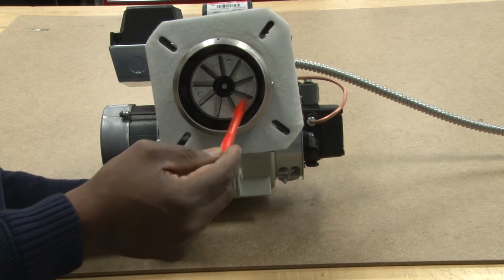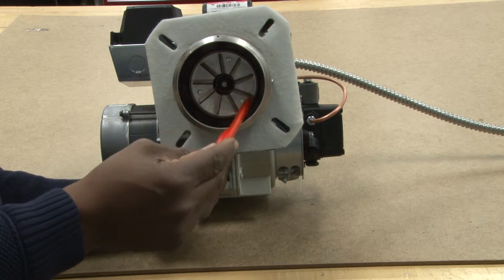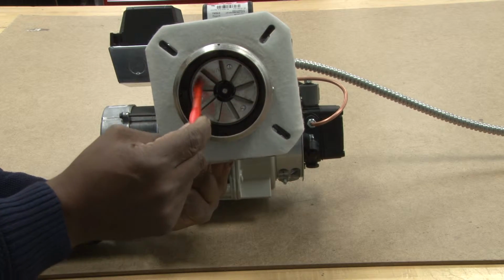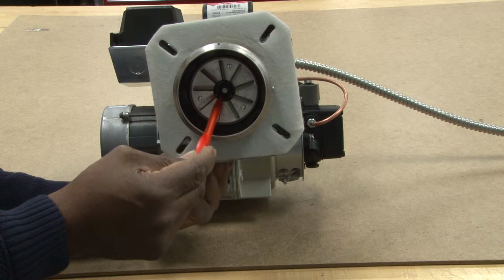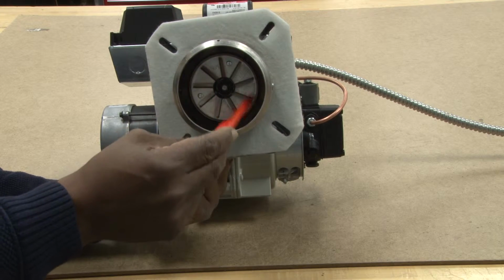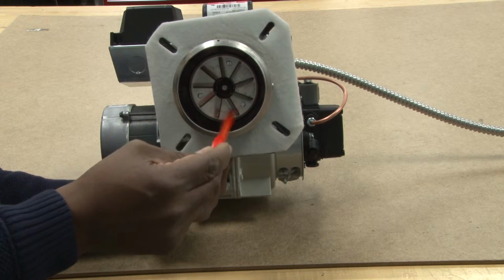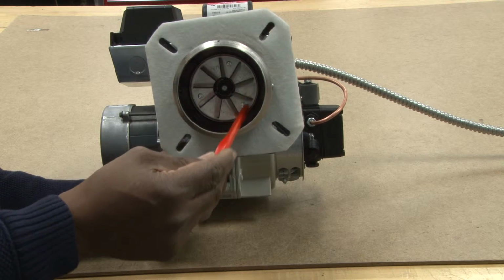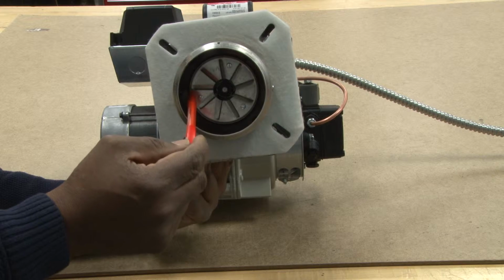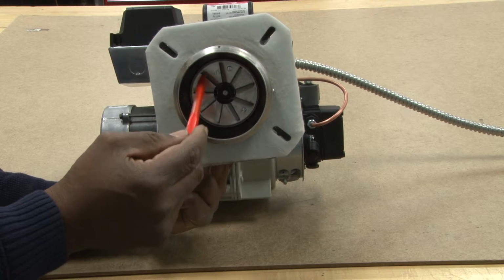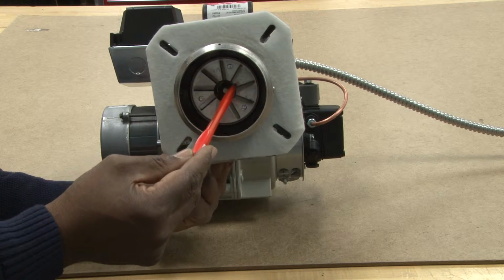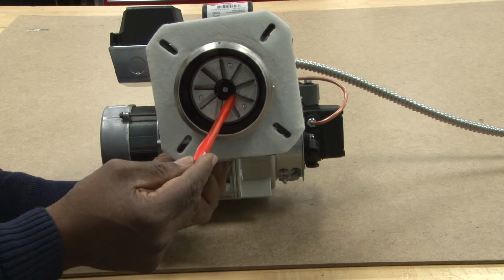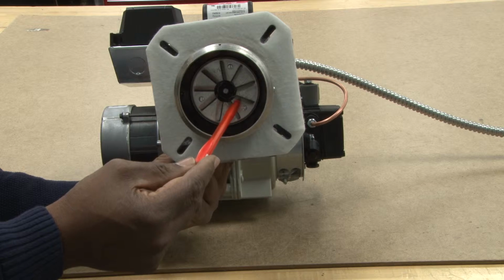This is a retention head. It's almost like a turbine, but it's a retention head which is designed to swirl air with the oil, which is in a mist, to create a certain type of flame pattern. There are many different flame patterns you may have. One may be a hollow cone or a solid cone, or a combination of both.